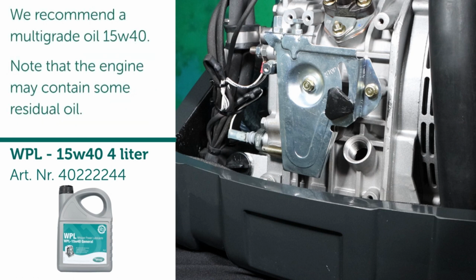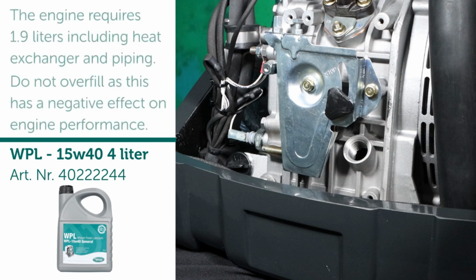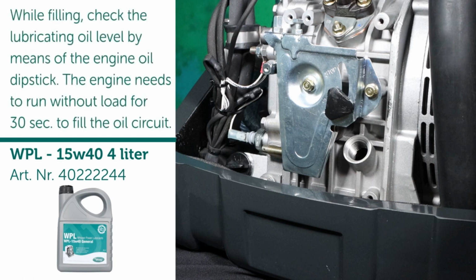We recommend a multigrade oil 15W40. Note that the engine may contain some residual oil. The engine requires 1.9 liters including heat exchanger and piping. Do not overfill as this has a negative effect on engine performance. While filling, check the lubricating oil level by means of the engine oil dipstick.